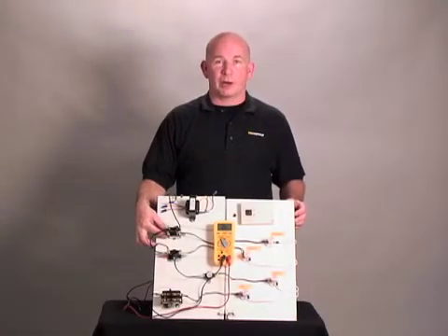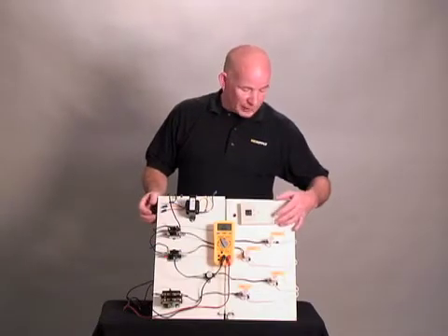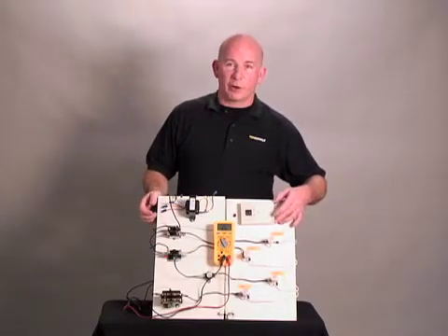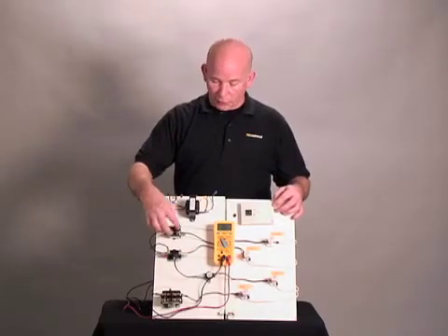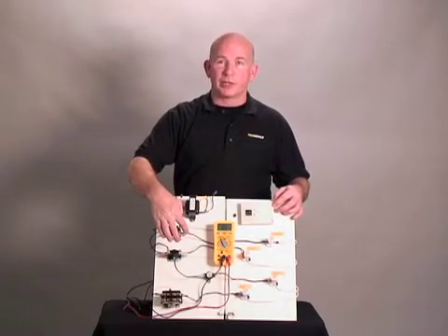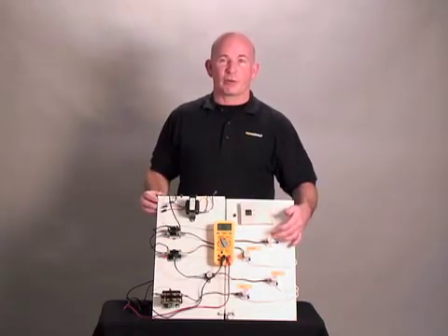Now that we have our fan relay wired, we can energize the 24 volt relay by simply turning the fan motor from auto to on. Once we do that, the normally closed contacts will open. The normally open contacts will close, sending a current flow to our light over here which represents our indoor fan motor.